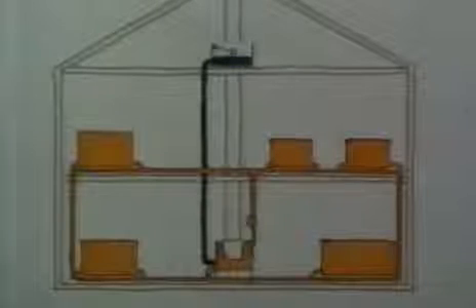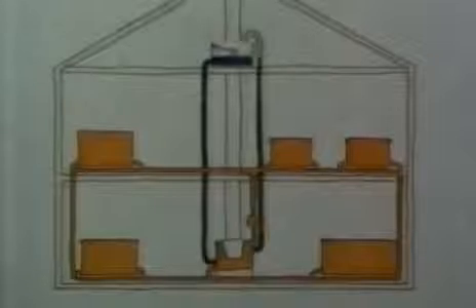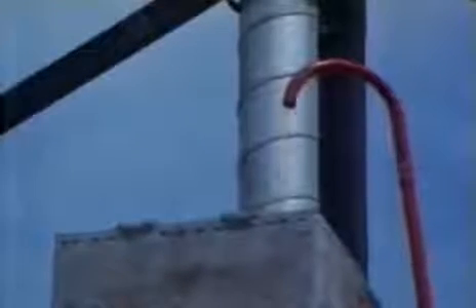The pipes round the boiler do look a bit complicated. There's one pipe to a tank in the roof to fill the system with water. There's also a vent pipe which lets the water inside expand as it heats up and lets water and steam out in case it boils. Here we've deliberately overheated this system and the steam harmlessly comes out of the vent, while fresh water comes in through the feed pipe to stop the boiler boiling dry. Of course, this doesn't normally happen, and the boiler is actually rather inaccurately named, as the water's never intended to boil.